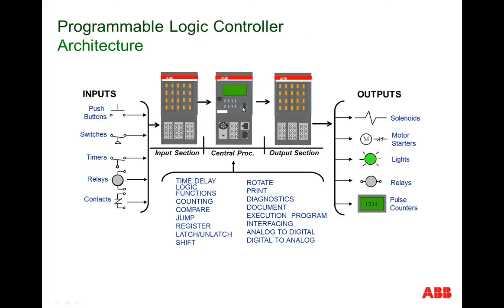Then this central processing unit communicates to output hardware, which also has lights that show an on-off status of each of the outputs that are wired into the system. What's nice about moving from relays to a central processing unit like this is that you can do some fairly in-depth computer-based functions, not only time delays and logic functions, but now shift registers, diagnostics, documentation, analog to digital and digital to analog conversions, and so on and so forth. So the system can get fairly intuitive and hook up to a variety of different types of equipment. This is called a programmable logic controller, and it's very prevalent in industry.